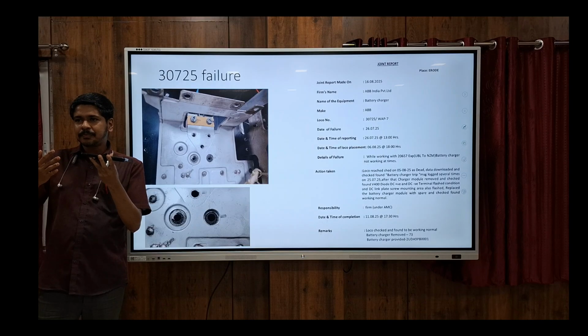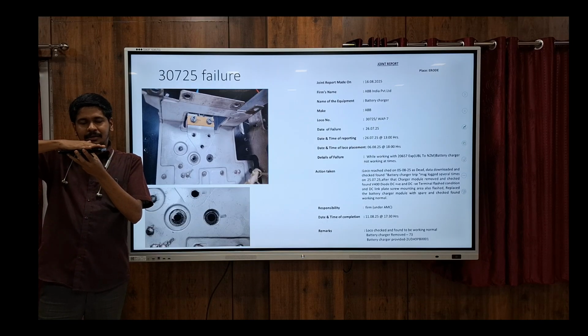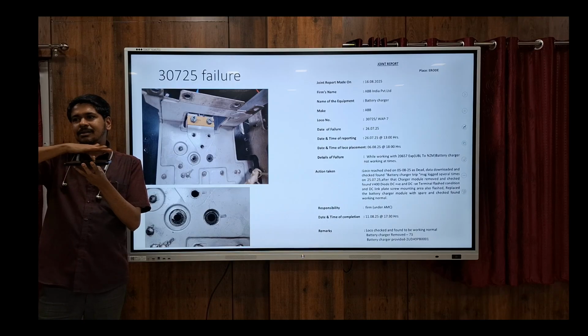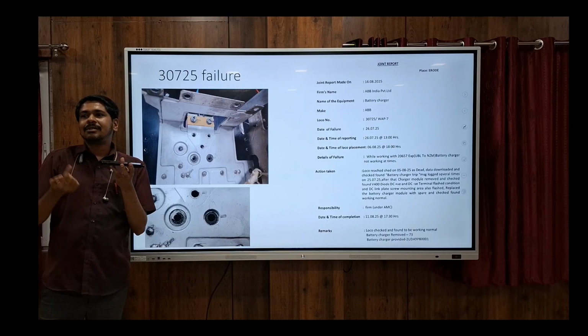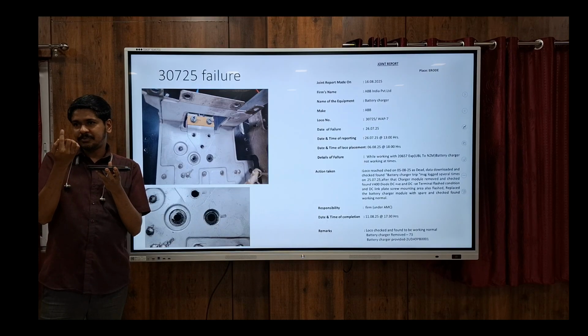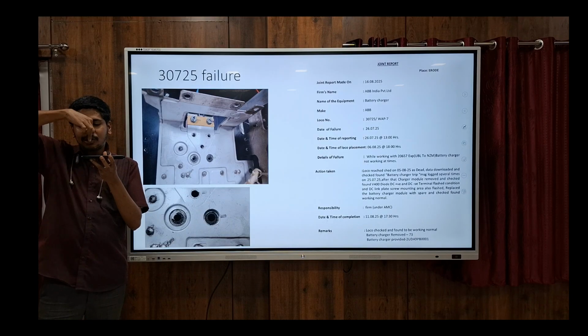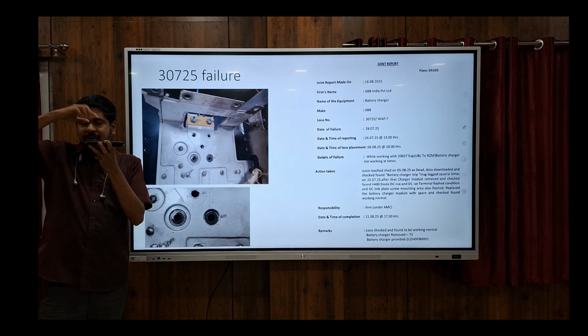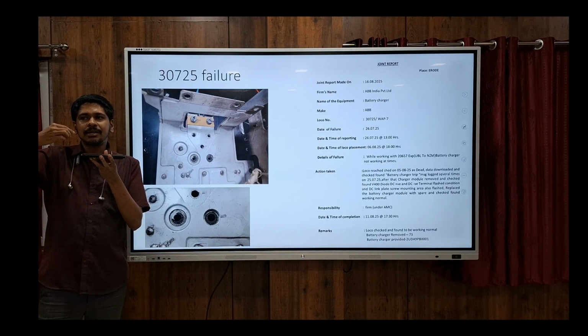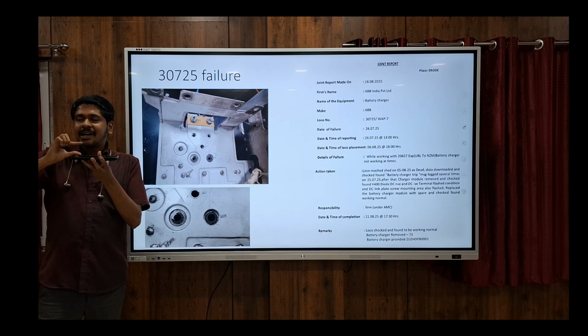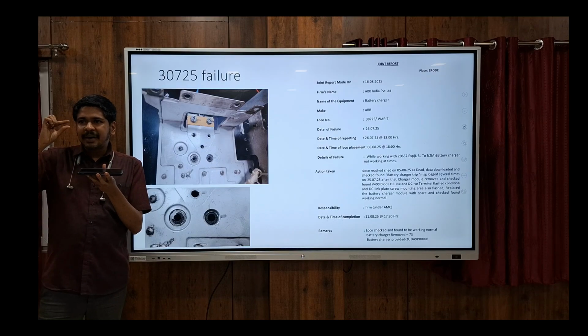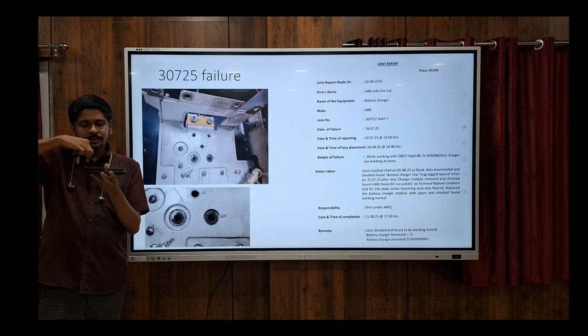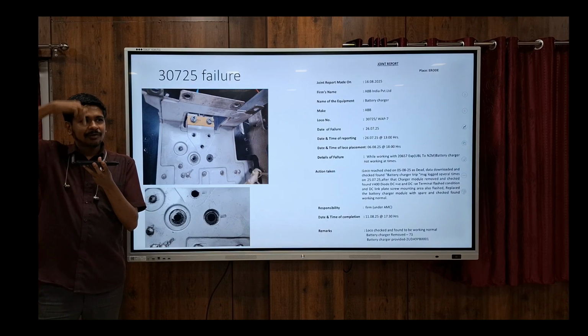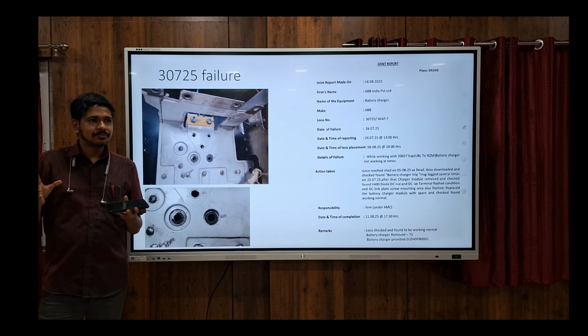The IGBT was there like this, and inside the IGBT substrate, it is made by silicon-like components. What happened is, they used a bolt of excess length. So the bolt would go inside. From outside, when we look, we would see that the bolt is not fully tightened. Two things it can cause: it will make the separation between the plates different, and second, the substrate inside — it will go and hit that substrate also.